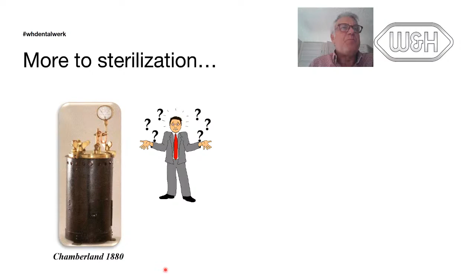There are many machines on the market. You have these machines from 1880, a long time ago, and these new devices. I know in your area, in your country, you still use a lot of dry heat sterilizers. The problem with dry heat is the heating time. I remember when I visited your country that people talked about 100 degrees Celsius for 15 to 30 minutes. This is not enough. First of all, the time is after preheating. So when we talk about 30 minutes, this is the sterilization phase time, the exposure to heat. And 100 degrees is by far not enough. It must go to at least 180 for half an hour. So we have preheating 15 minutes, half an hour, plus half an hour. Or if you go to 160, it even takes 2 hours at the plateau. Only in this case can you sterilize, can you kill all microorganisms.